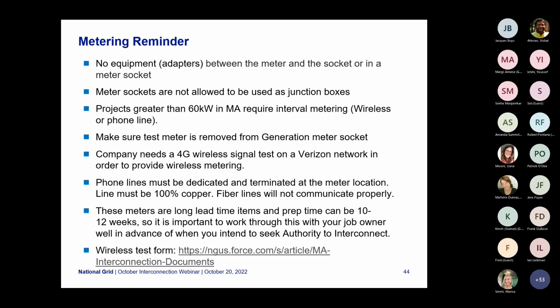Just some reminders with respect to metering. No equipment or adapters between the meter and the socket or in a meter socket. Meter sockets are not allowed to be used as junction boxes. Projects greater than 60 kW in Massachusetts require interval metering, wireless or phone line. Make sure that the test meter is removed from the generation meter socket. The company needs a 4G wireless signal test on a Verizon network in order to provide wireless metering. Phone lines must be dedicated and terminated at the meter location. The line must be 100% copper. Fiber lines will not communicate properly. These meters are long lead time items, and prep time can be 10 to 12 weeks. So it's important to work through this with your job owner well in advance of when you intend to seek the authority to interconnect. And you can find the wireless test form at the link noted here at the bottom of the page.